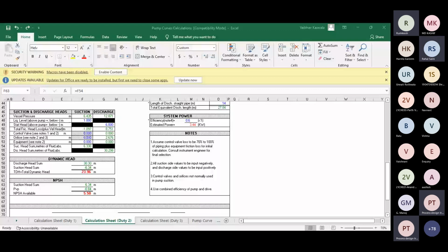सपोज आप जब बता रहे ना, अब मैंने आपको जब हमने सिस्टम कर्व, डिस्चार्ज वाल्व थ्रोटल किया था, यस मैंने जो आपको सिस्टम कर्व दिखाया था जहाँ पे कुछ स्टैटिक हेड था और कुछ फ्रिक्शनल लॉस था, तो वहां पे स्टैटिक हेड बढ़ा देंगे तो दैट्स व्हाई योर प्रेशर इज इंक्रीजिंग। आपका पंप का जो डिस्चार्ज प्रेशर है दैट इज प्रेशर, दैट इज नॉट द पंप हेड। उसको आप डिस्चार्ज हेड भले बोलते हो लेकिन उसको डिस्चार्ज प्रेशर बोलना है। वेंडर आपको हमेशा बोलेगा मेरा हेड 30 मीटर है पंप का, आप कभी ये नहीं बोलोगे कि मेरे पंप का डिस्चार्ज प्रेशर है 3 kg या 30 मीटर्स। Head is always constant, head is the property of the pump, it will always remain constant. Is it clear?